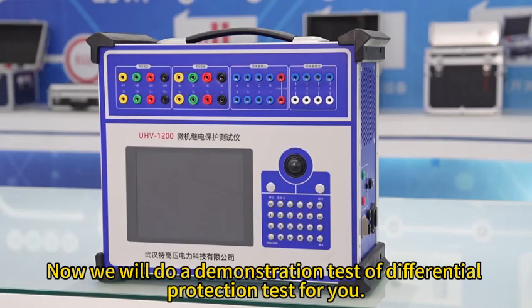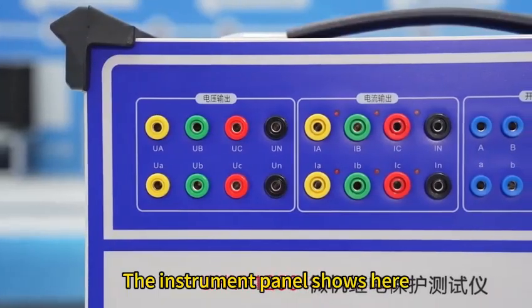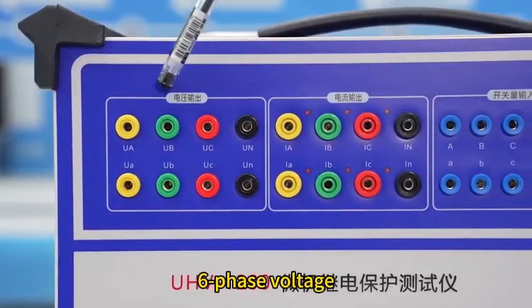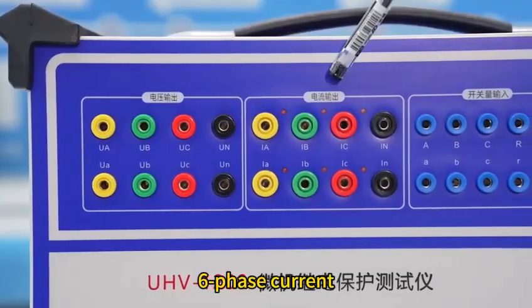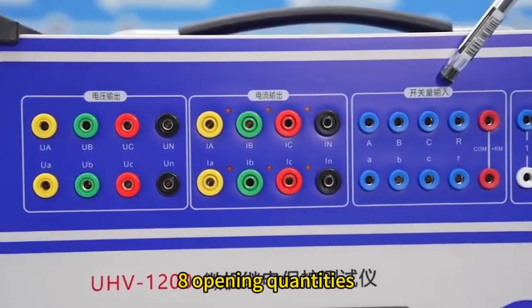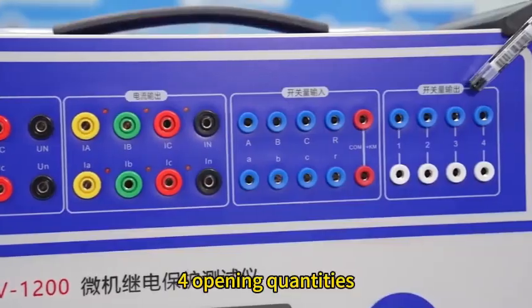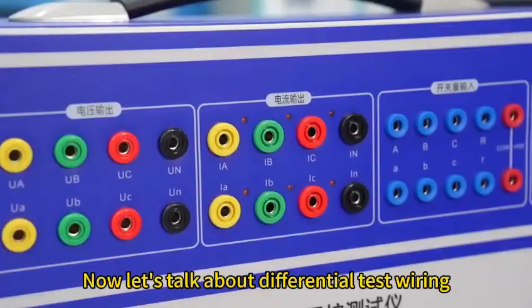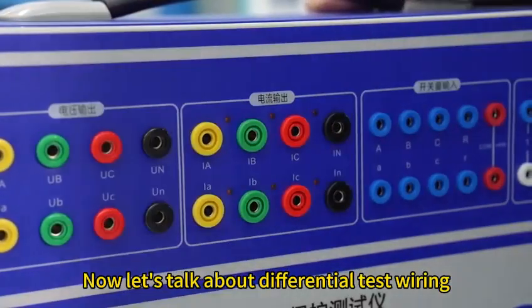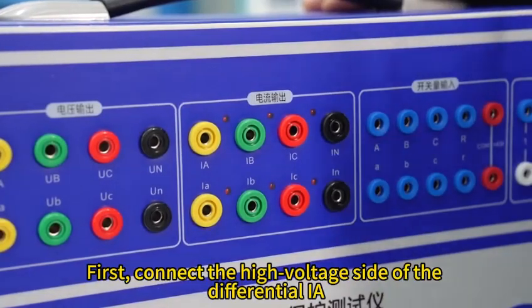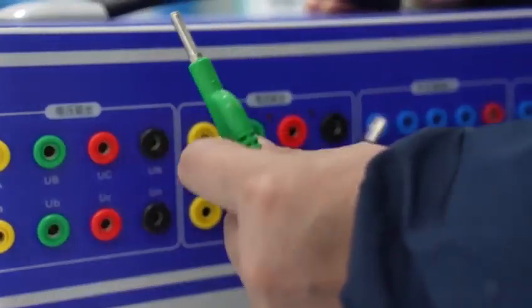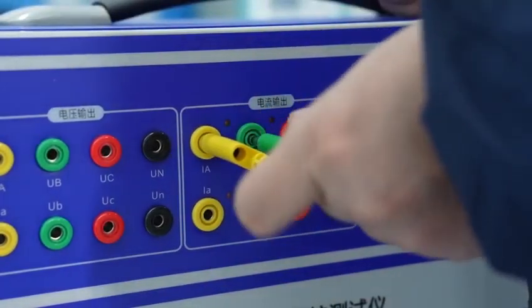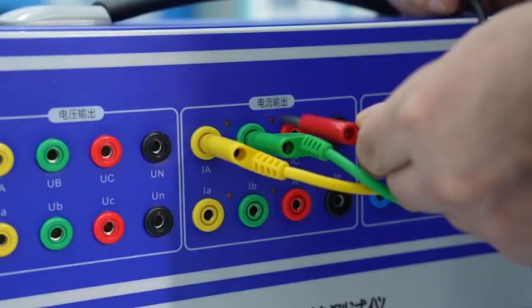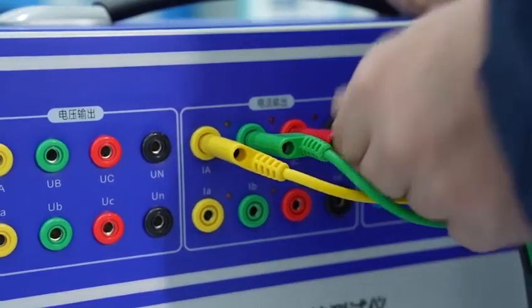Now we will do a demonstration test of differential protection test for you. The instrument panel shows here 6-phase voltage, 6-phase current, 8 opening quantities. Now let's talk about differential test wiring. First, connect the high voltage side of the differential IA, IB, IC, and IN.